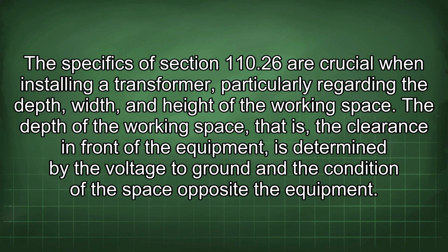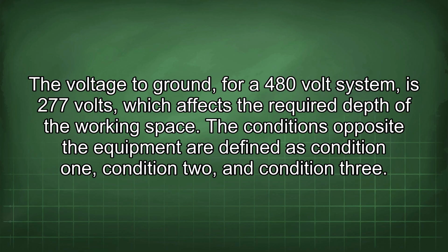The specifics of Section 110.26 are crucial when installing a transformer, particularly regarding the depth, width, and height of the working space. The depth of the working space, that is, the clearance in front of the equipment, is determined by the voltage to ground and the condition of the space opposite the equipment. The voltage to ground for a 480-volt system is 277 volts, which affects the required depth of the working space.